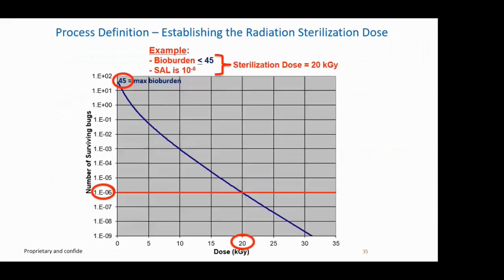We'll talk about that in a minute. This puts these doses into perspective. For those not familiar, this is the classic standard distribution of resistances in the 11137 standard, shown in table form. If you draw the curve, it looks like this. For a bioburden of 45, the curve goes down and intersects the SAL 10 to the minus 6 line at 20 kilogray. So that's the relationship between 20 kilogray and a bioburden of 45.